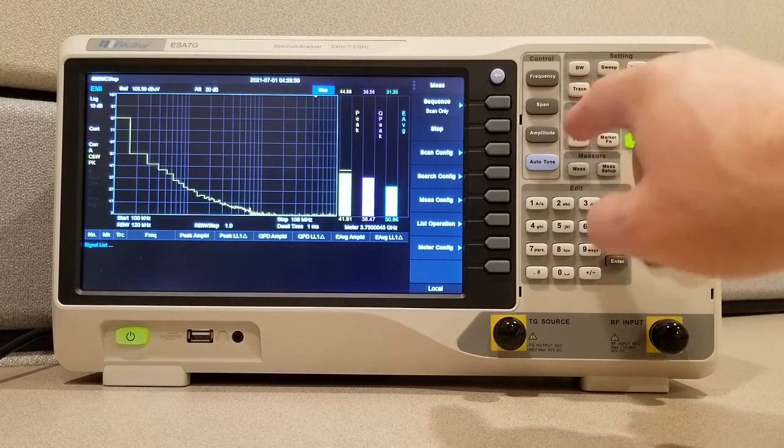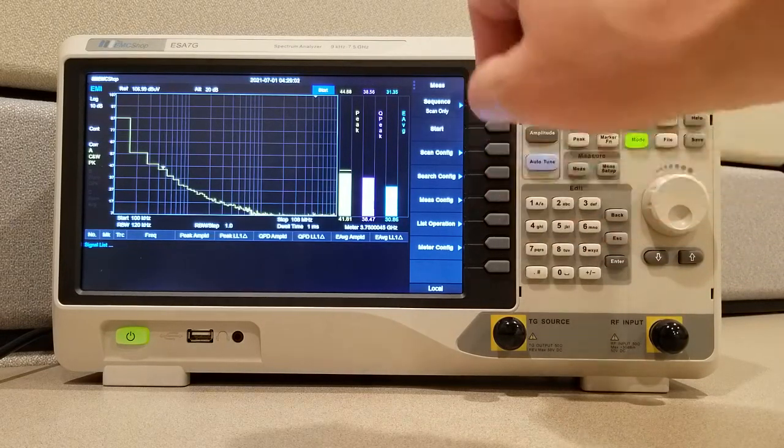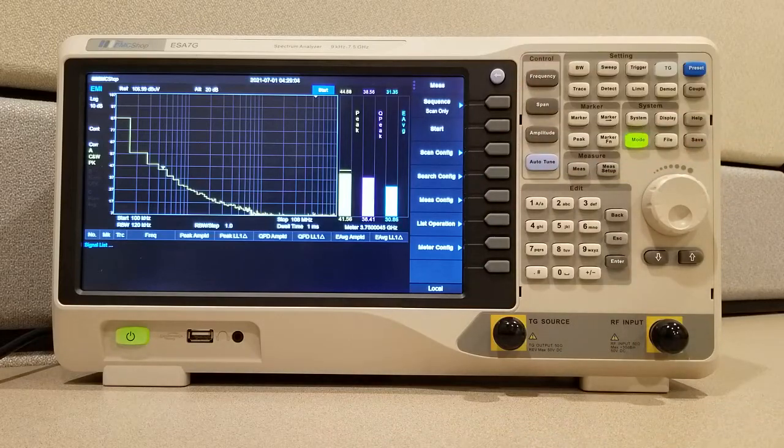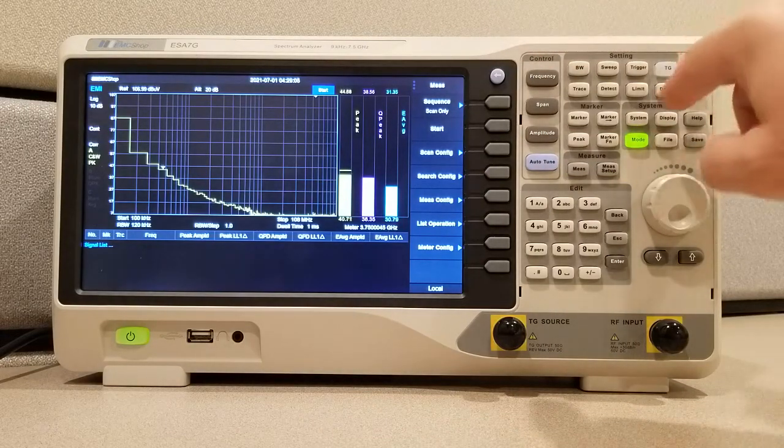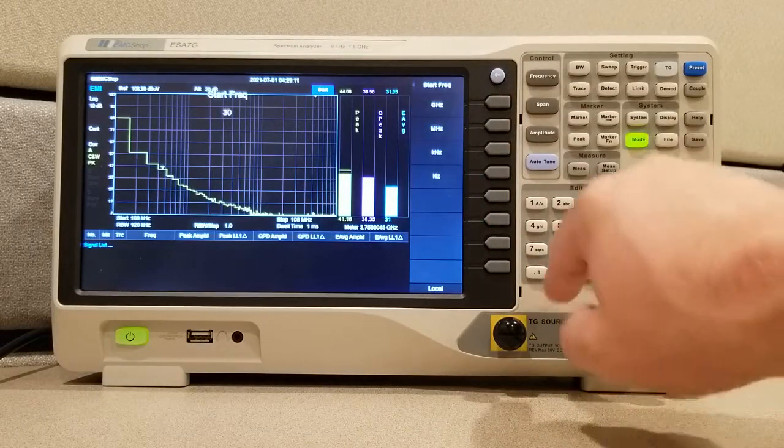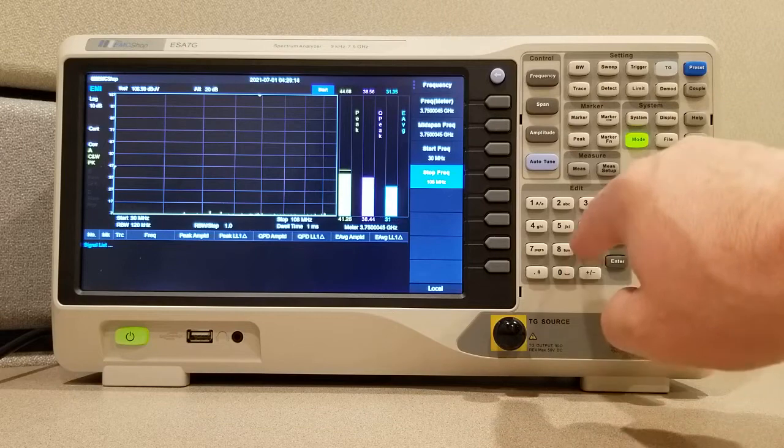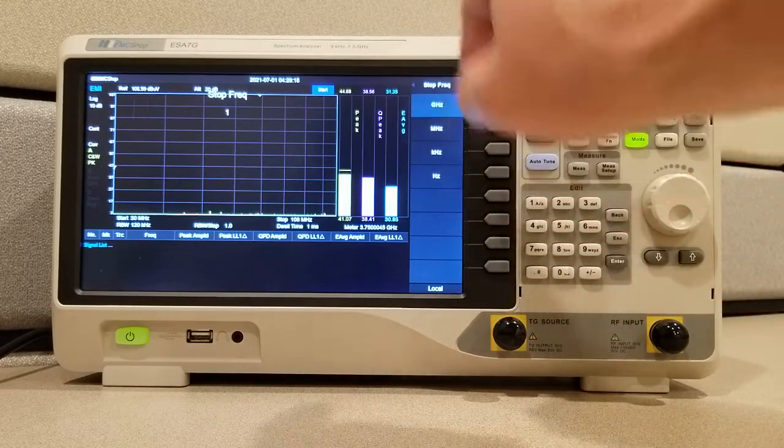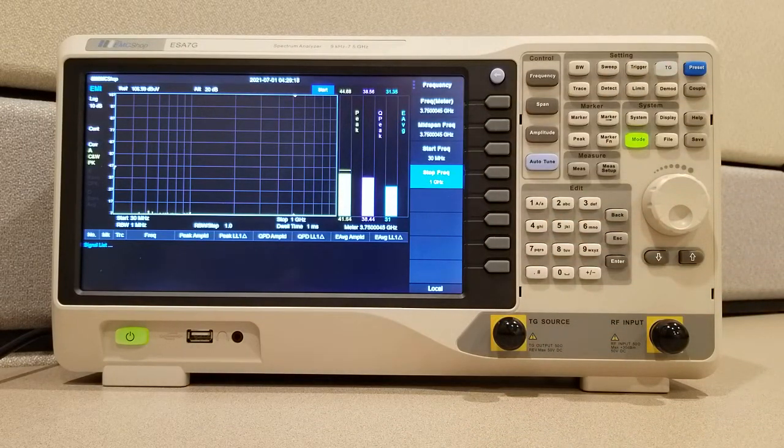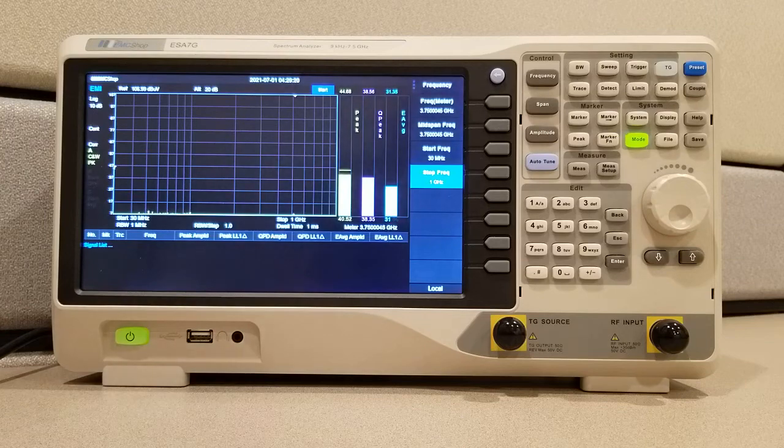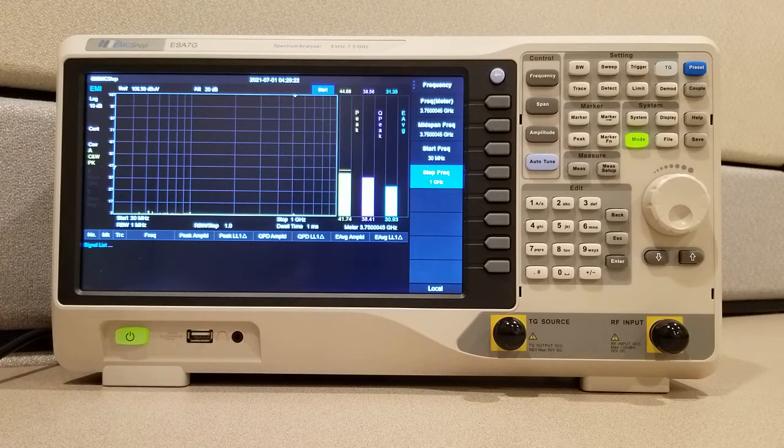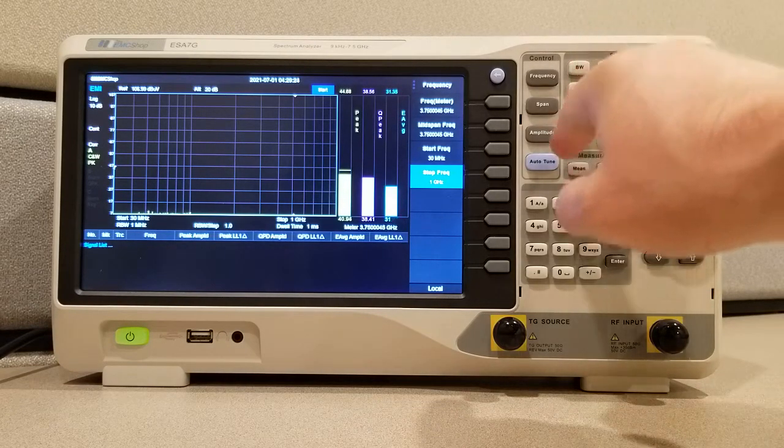Now for limits. We will stop this again. And let's set up our frequency limits to start at 30 megahertz. And we're going to stop at 1 gigahertz. And that's because today I'm going to show you how to load the FCC part 15b limit into this device.